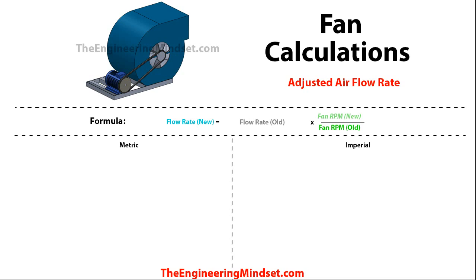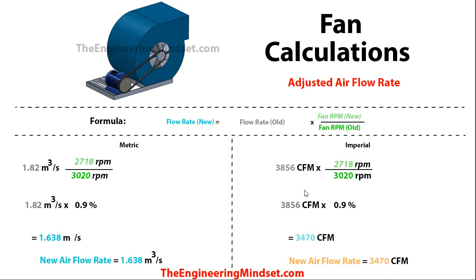Now if you have made any changes to the fans and motors, then we want to know what the adjusted airflow rate will be, and will it satisfy the design criteria? Or are we making a reduction in order to reduce the airflow rate to make some energy savings? We can use this formula: the new airflow rate is equal to the old airflow rate multiplied by the new fan RPM divided by the old fan RPM. Sticking these figures in — we know the old flow rate and what the adjusted and original RPMs are — this brings us to 1.638 meters cubed per second, or 3,470 cubic feet per minute.